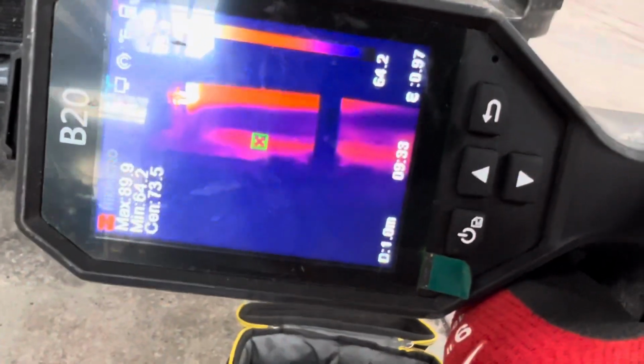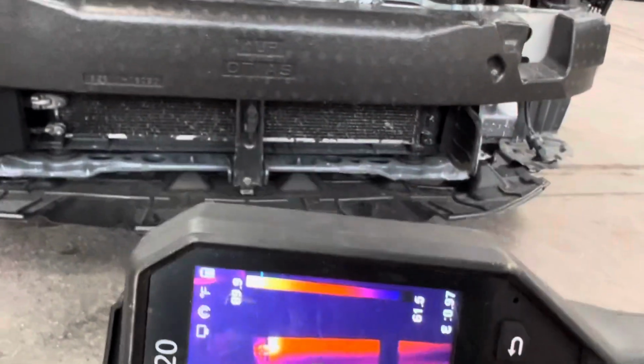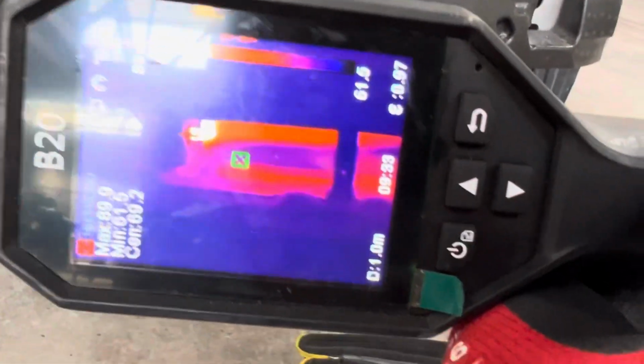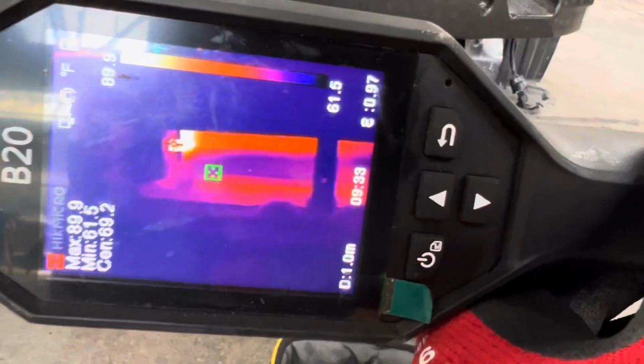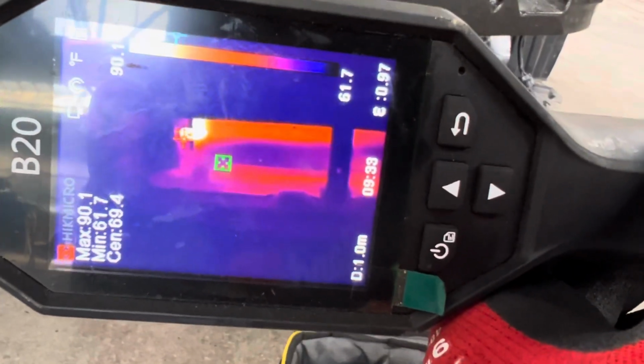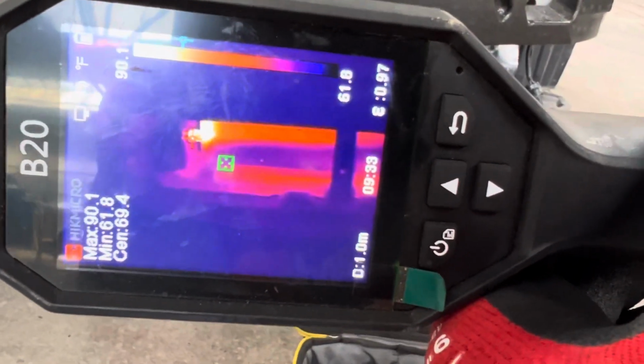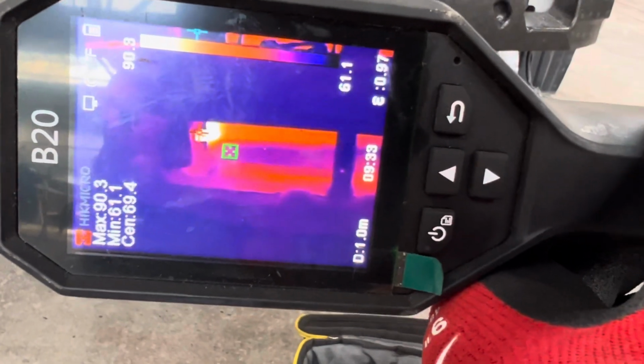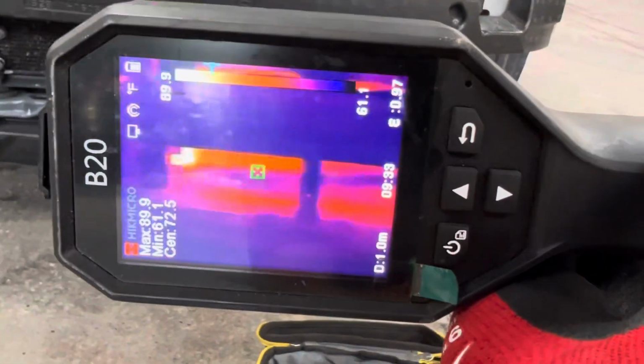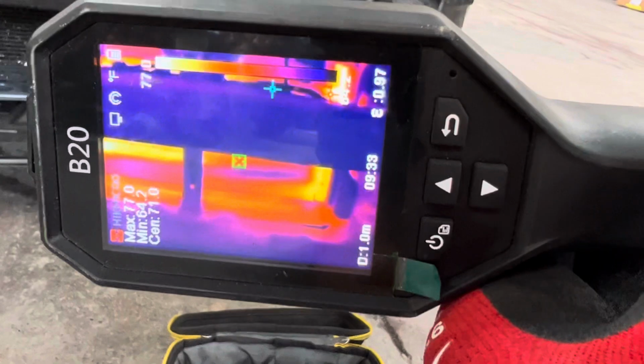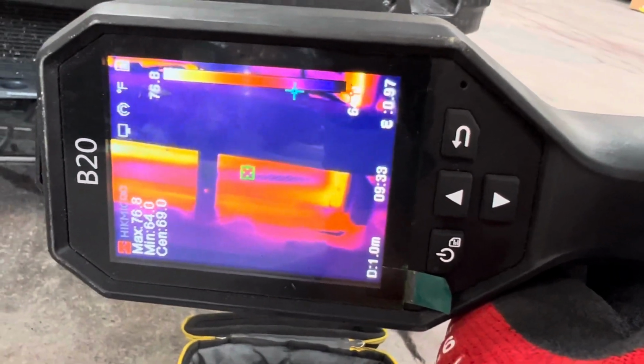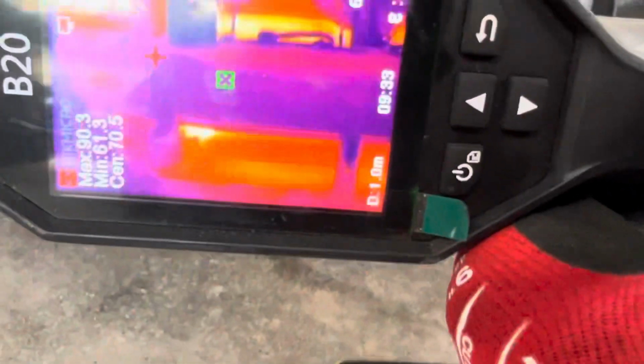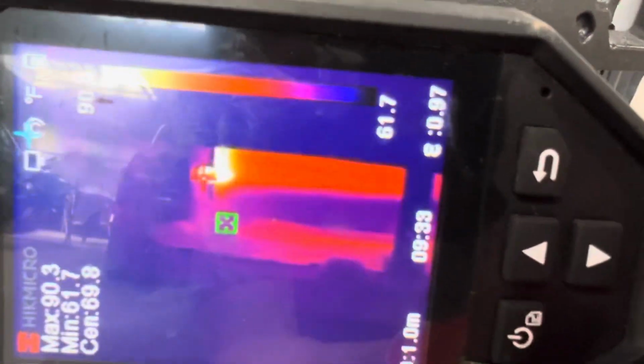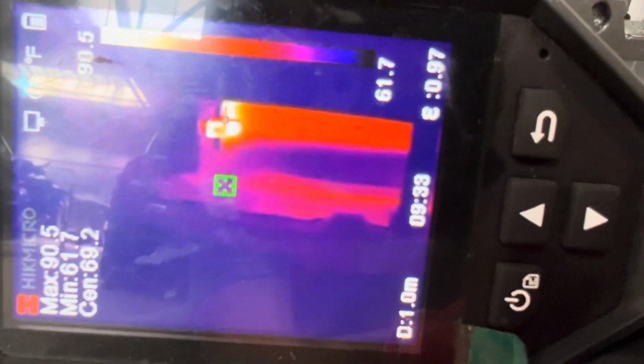There we go. So can you see the condenser? Do you see this hot picture? Do you see that dark line down there in the condenser? That is your liquid, that is your subcooling rows on your condenser. Your receiver is over there. You see how hot that receiver is? And do you see the heat coming in that upper fitting, how glowing red that is? So if you look where it says max, max, it's 90 degrees.